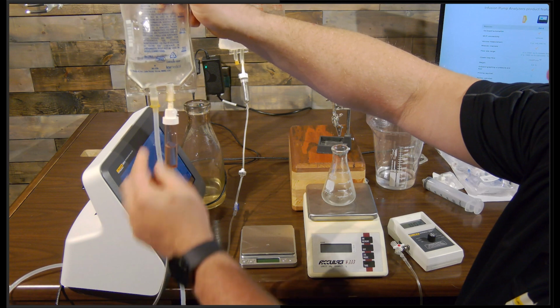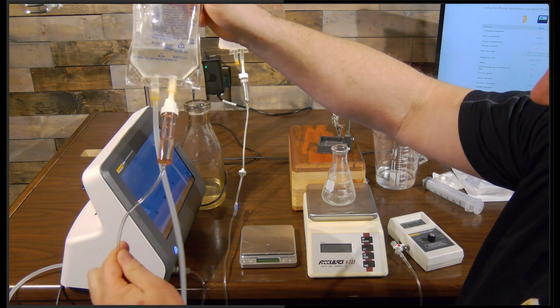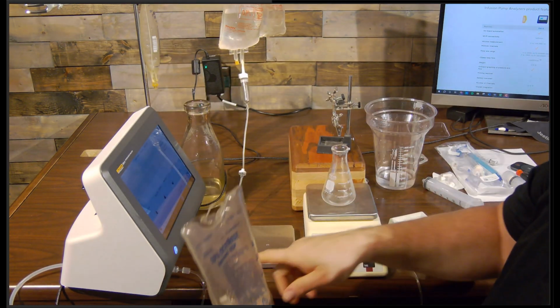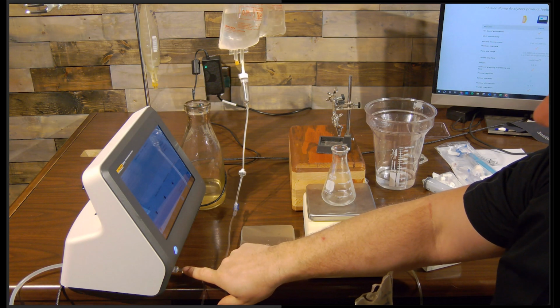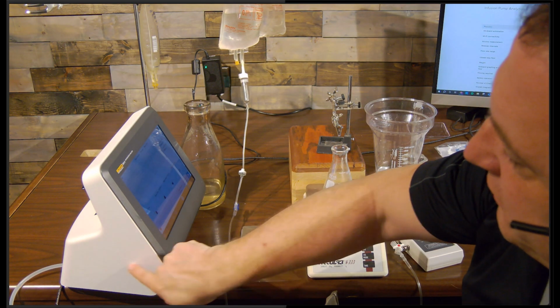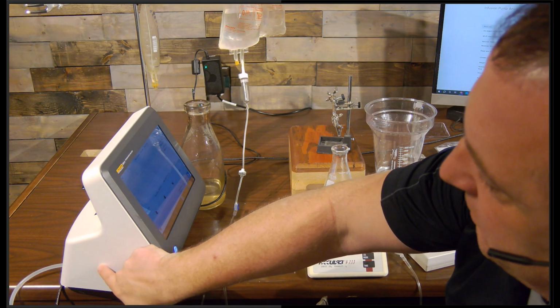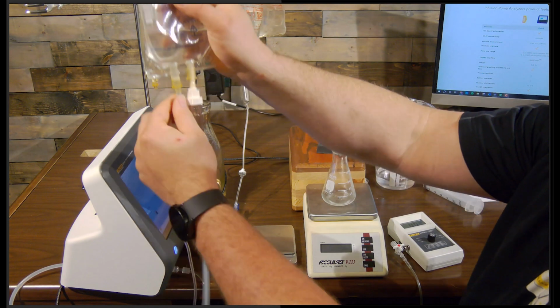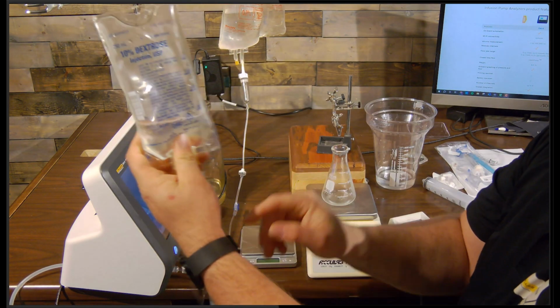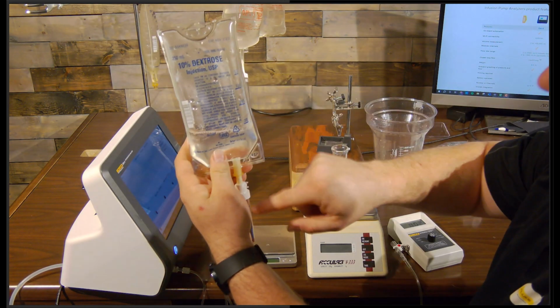You see we have two lines here. The fluid comes out of the bag, down the test tubing, through the infusion pump, into the front of the IDA-6. And it uses a piston-driven stepper motor inside. So as the fluid pushes the stepper motor back, once it's back, the pump pushes it back around, pushes the fluid back out and back into my bag. So I'm pretty much recycling this water the entire day. So I don't need to refill this bag.